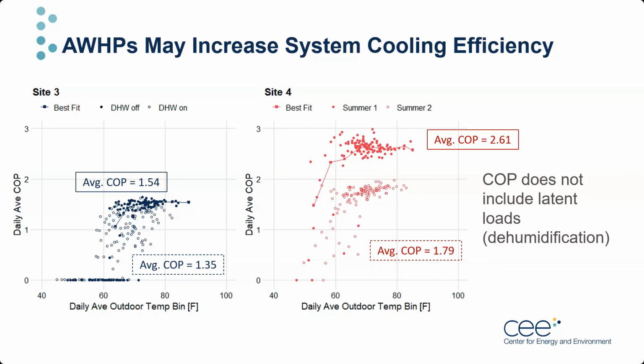Site 4 didn't have these penalties, but we still have two distinct efficiency regimes in this chart, with filled circles from summer 1 and hollow circles from summer 2. The average cooling COP from summer 1 was 2.61 compared to 1.79 in summer 2. This was tied to multiple adjustments being made by the manufacturer and installer, ranging from tweaking target supply temps to combining in-floor loops and even removing the external hydronic separator. These adjustments were primarily driven by heating performance, but they had an adverse effect on cooling season as a result.